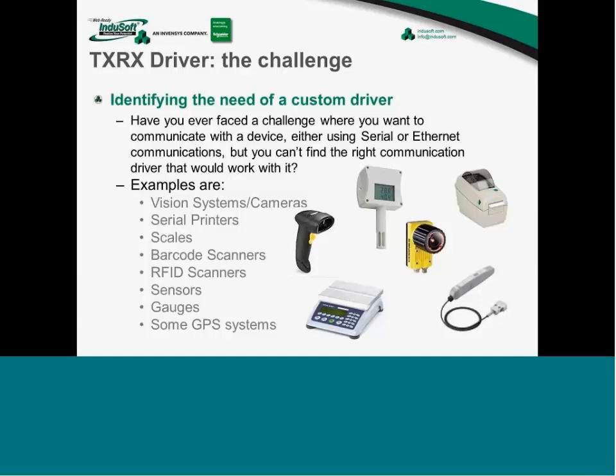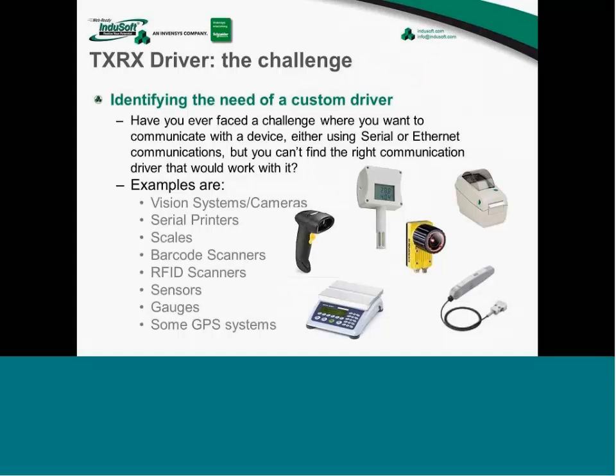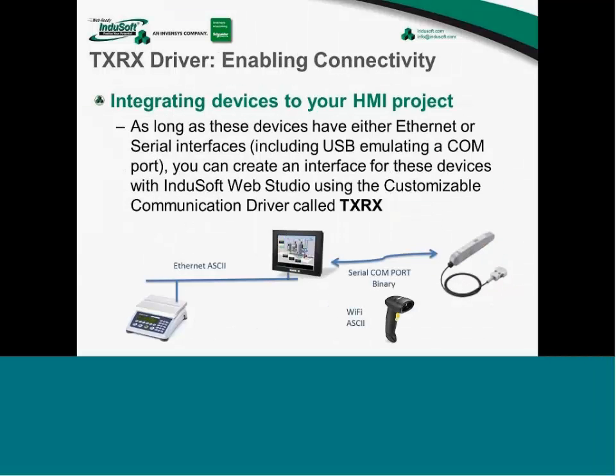Another use case: what if you want to receive unsolicited messages from a ControlLogix or CompactLogix PLC? Our ABCIP driver doesn't support receiving those, but you can configure the TXRX driver to listen on port 44818 TCP — the default CIP port — and if the PLC sends a message, you get it into a tag. Those are some typical usage scenarios for the TXRX driver.